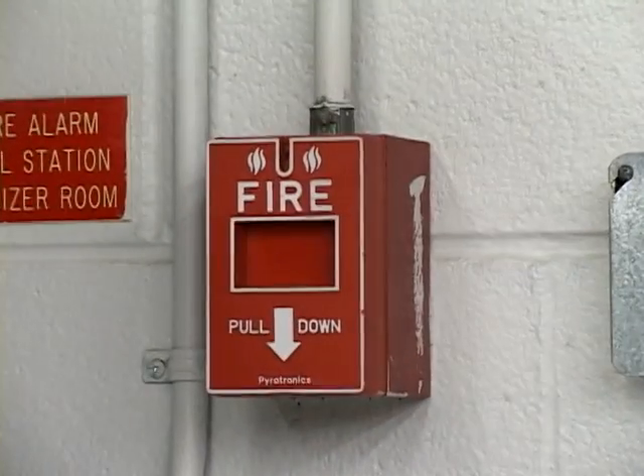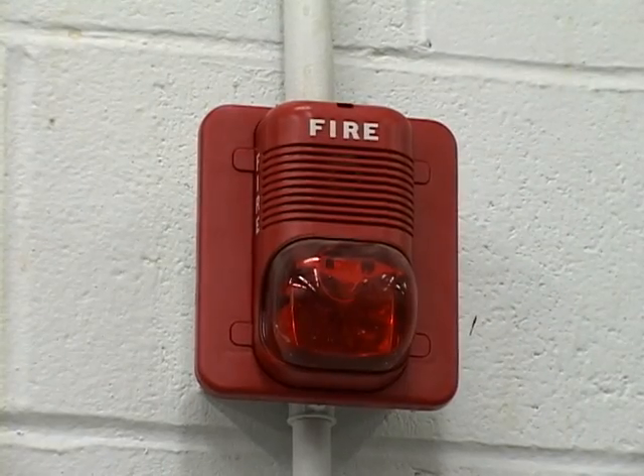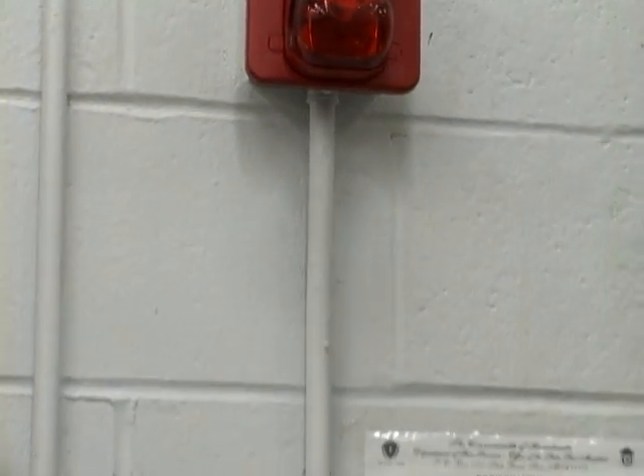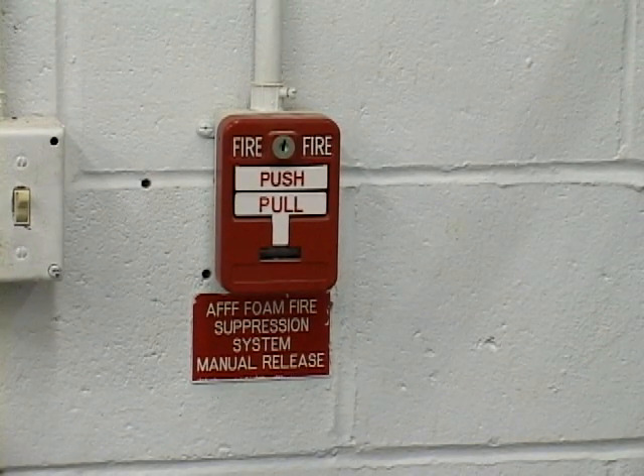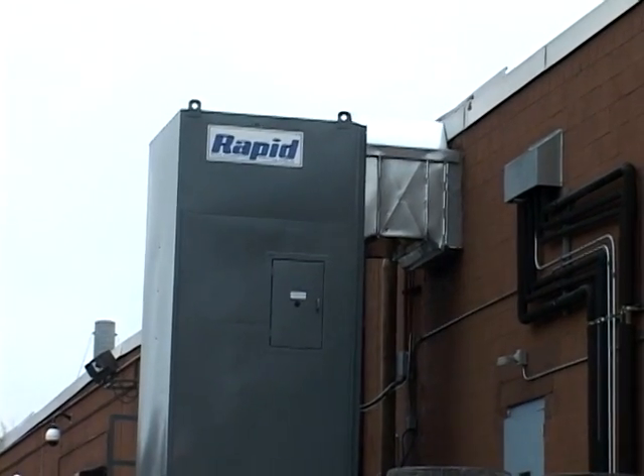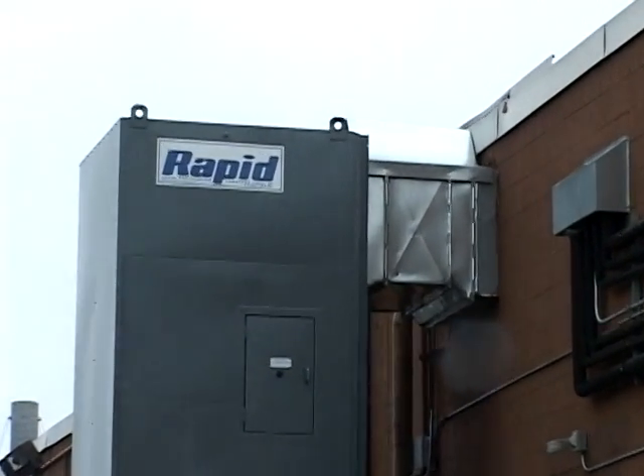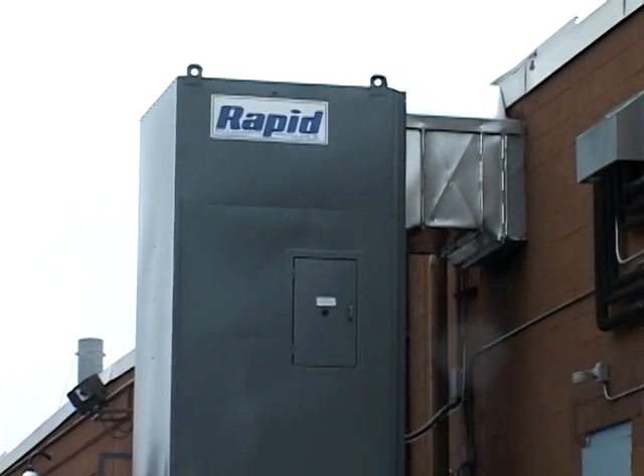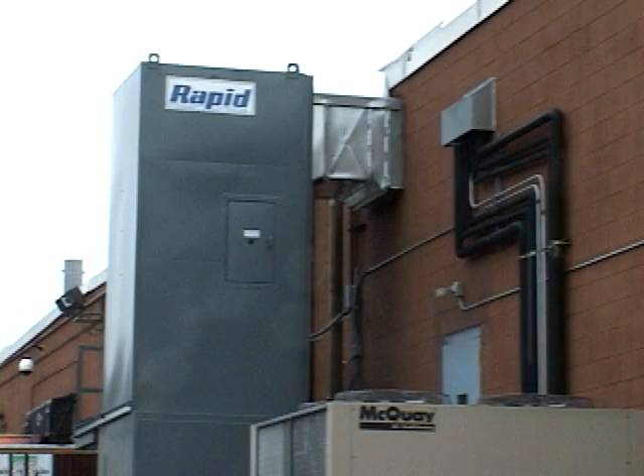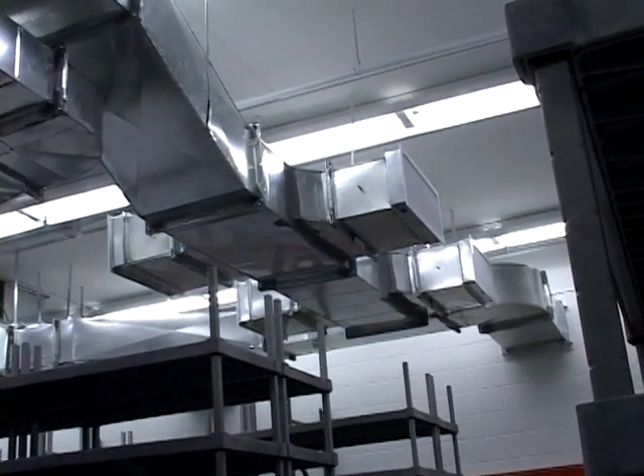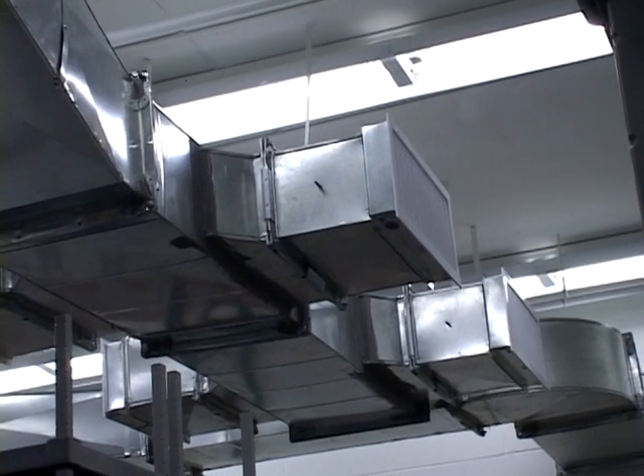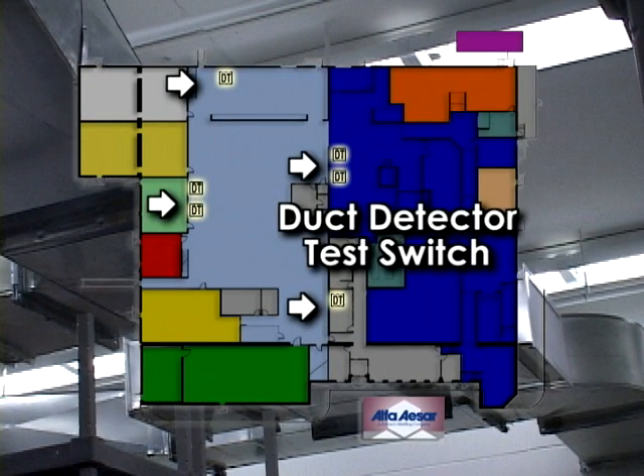The fire alarm system in the building includes manual pull stations at exit discharge locations and top-of-stair locations, as well as any corridor areas where travel distance to an exit is 200 feet or more. Mechanical system monitoring includes duct-mounted smoke detectors to monitor supply-side ductwork of all HVAC air handlers moving more than 2,000 CFM. In some instances, this requires 2 detectors to ensure proper distances downstream from elbows, bends, and other turbulence-causing elements of the ductwork. The duct smoke detectors are provided with remote test indicator and reset buttons. These are located in corridor areas outside the space served by the associated unit and are prominently identified.